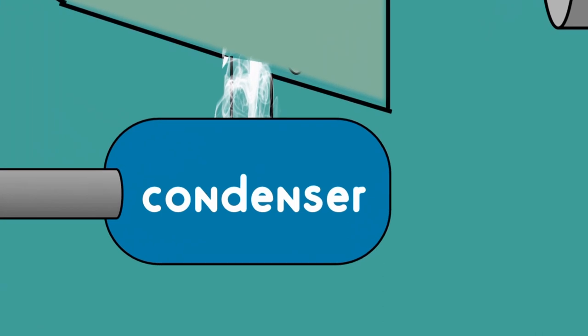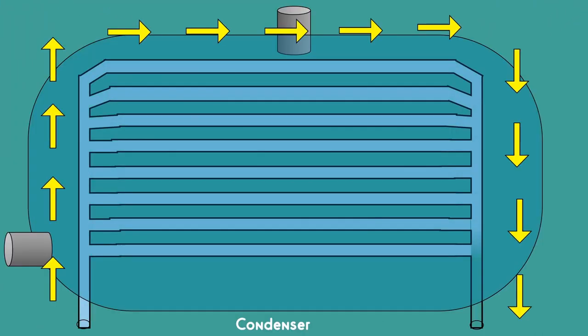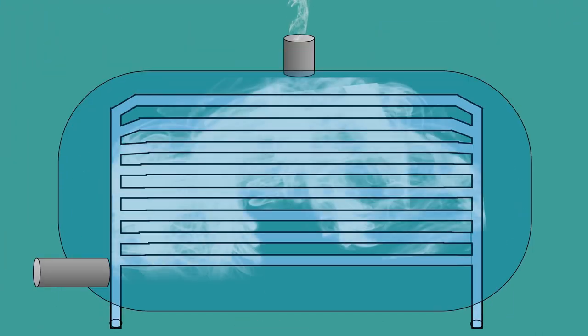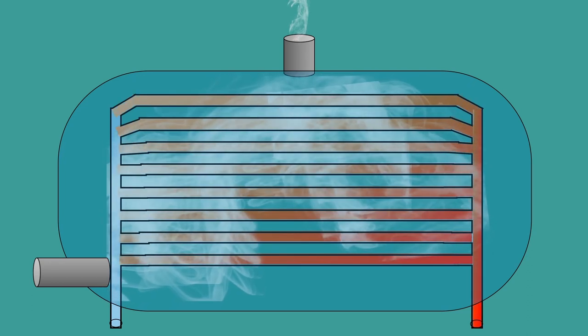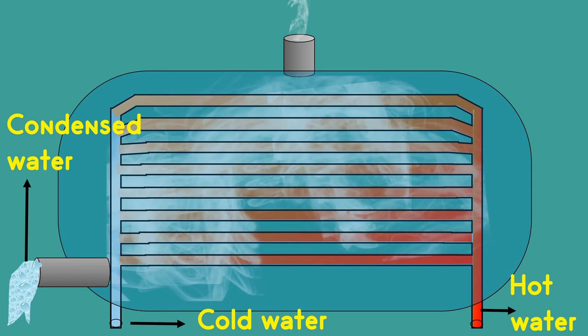In the condenser a stream of cold water flows through the tubes. When the hot steam enters the condenser the heat is transferred from this high temperature steam to the cold water. As a result steam cools and condenses to water, whereas the temperature of cold water increases due to this heat exchange process.